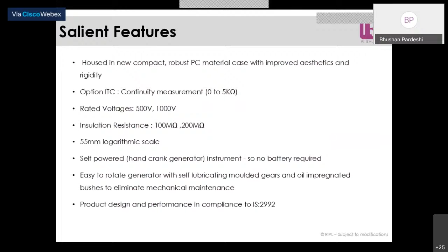So this is another analog insulation tester, but this comes in 5 kV test voltage. Basically, in this we provide three types of testing: hand crank type, battery operated, and mains operated on 230 volt. So you can use this meter in all three types. It has a resistance measurement from 10 kilo ohm to 1 tera ohm, with a test voltage from 100 volts to 5000 volts, as you can see in the presentation.